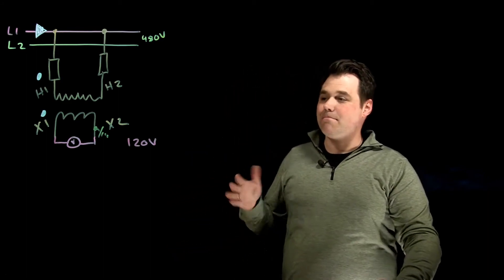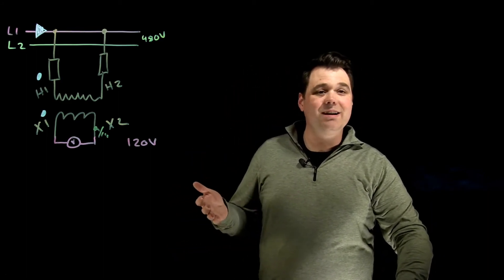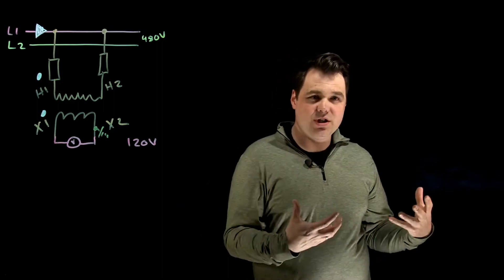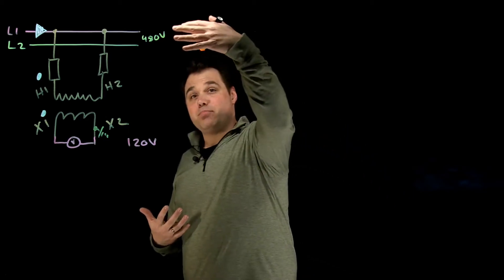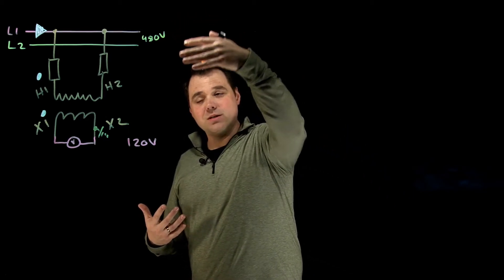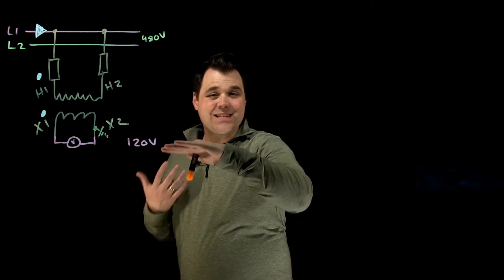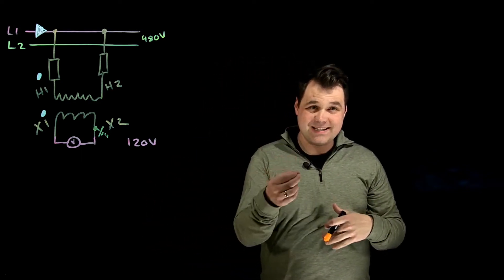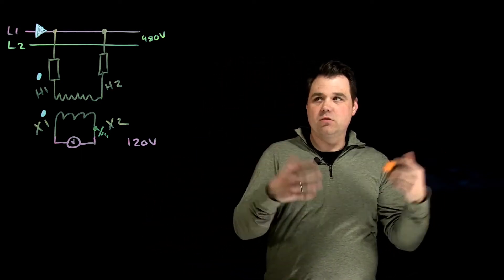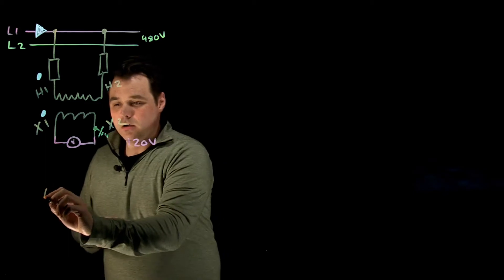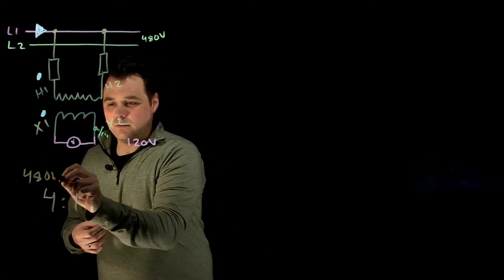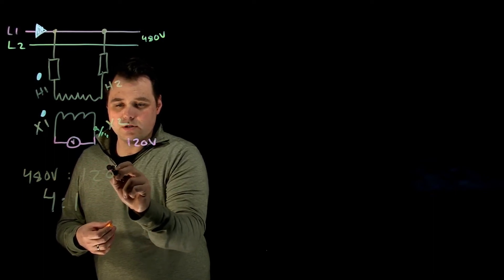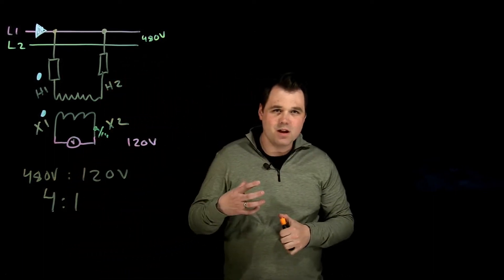Now when we look at these meters, the thing to keep in mind is they are all about a ratio, a transformer ratio. In this case here, my primary is 480 volts. My secondary is 120 volts, the rated voltage. So of course, this would be a four to one ratio. 480 volts to 120 volts.